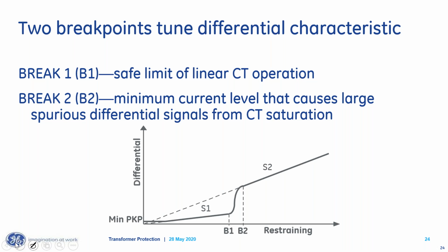You got two other questions I want to address. Okay, time. Well, I didn't get through minimum pickup. You just have to yell at me, John, for going over time. Minimum pickup, I would never set that less than 10%. The reason for that is the CT inaccuracy. And you can be more conservative than that if you go to a higher quantity like 20% or 30%.